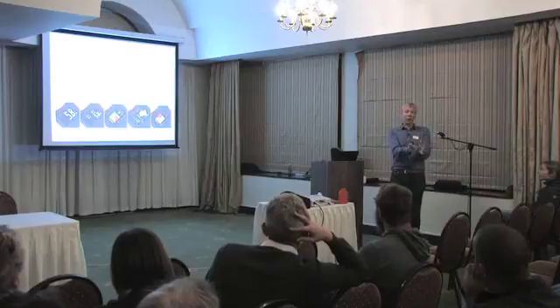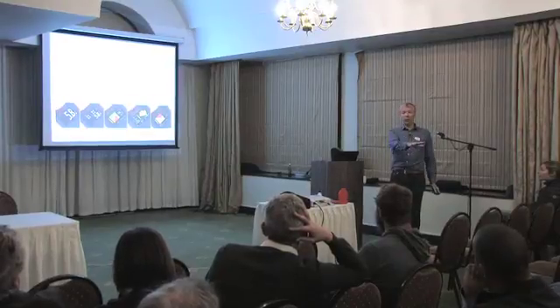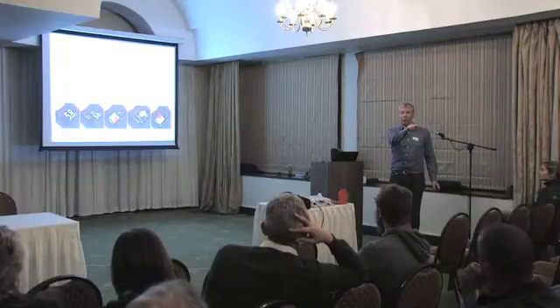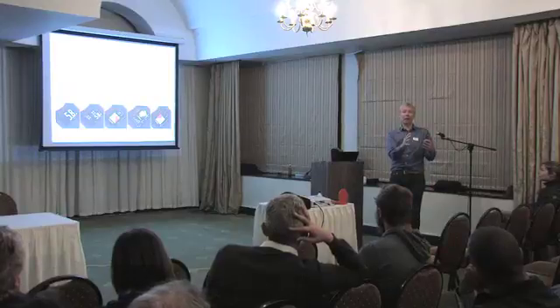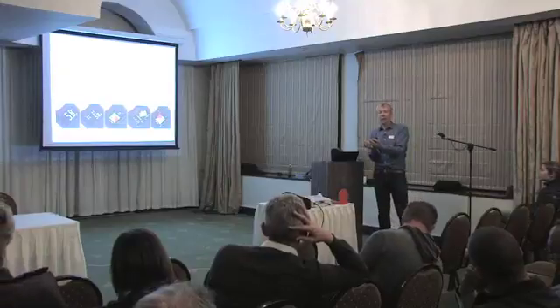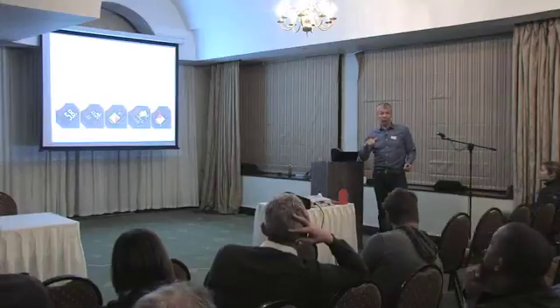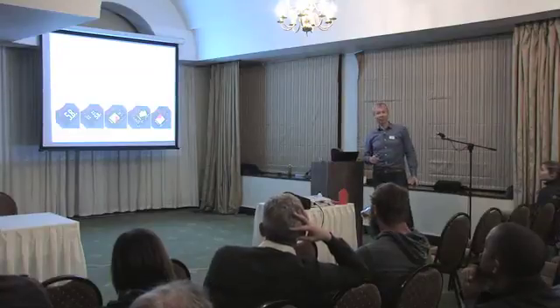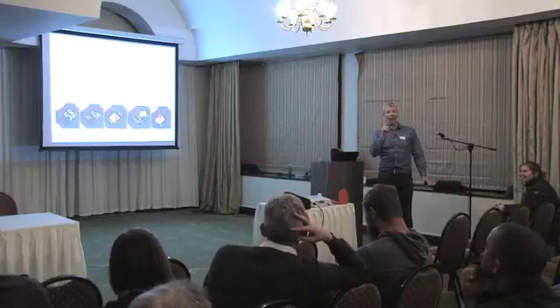The tiles have a known level of conductivity, and what you're doing by just putting them onto the gauge, it's comparing all the results of each point with all the 8 surrounding points and building a matrix and comparing what the tile says with what the gauge says. And it does it all inside its own test method, and it comes up and says either yes or no. As long as it says yes, you don't need to send it in for calibration. Yeah. That's the selling point.